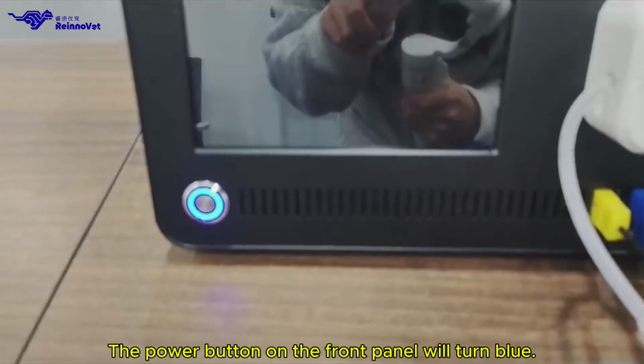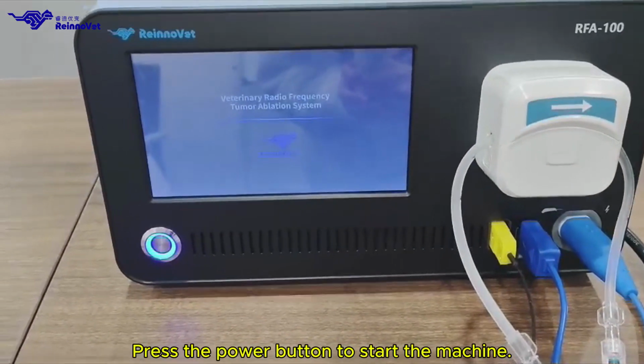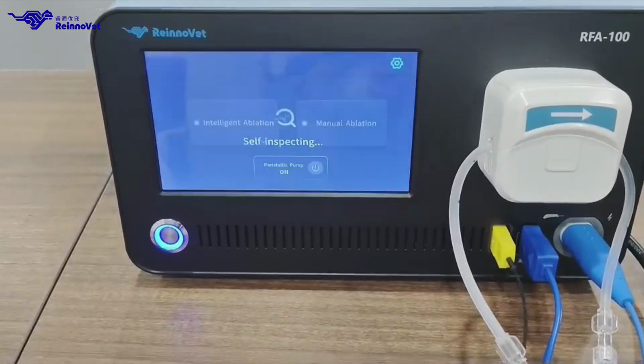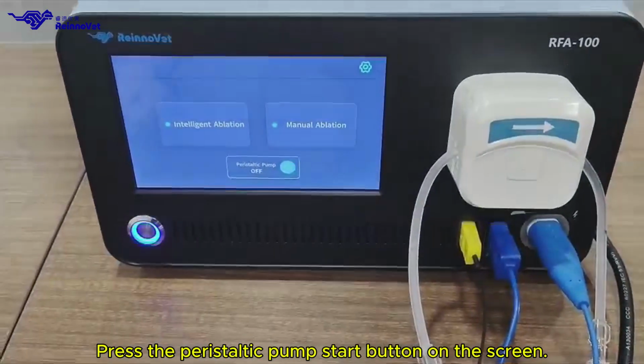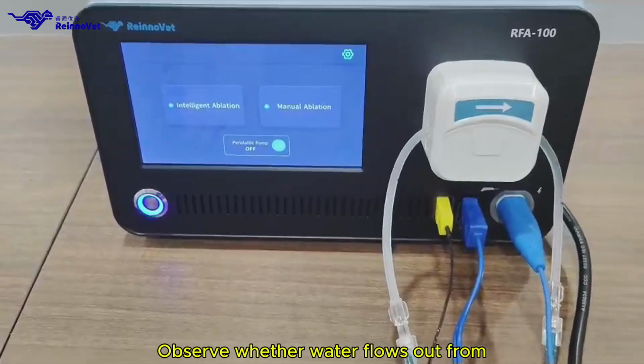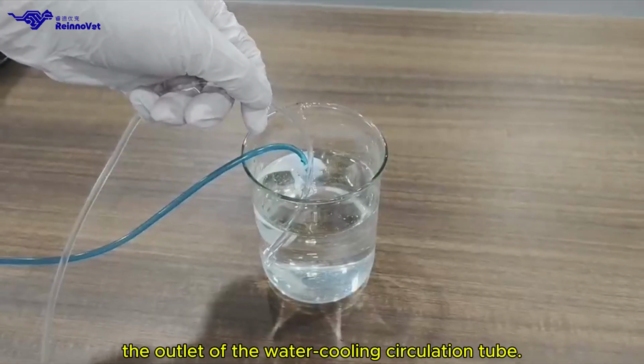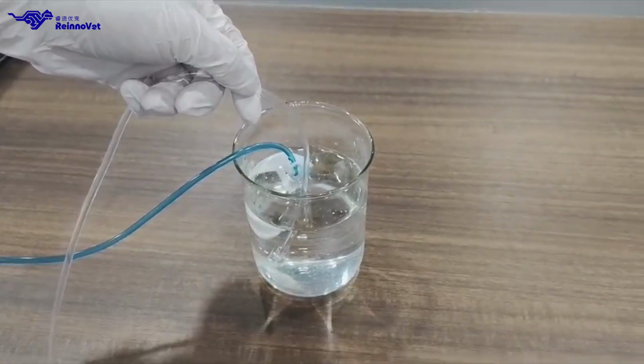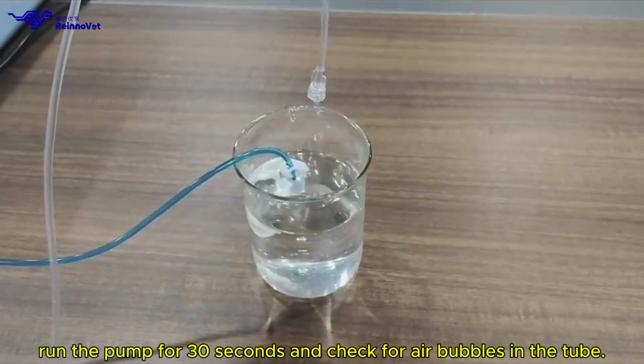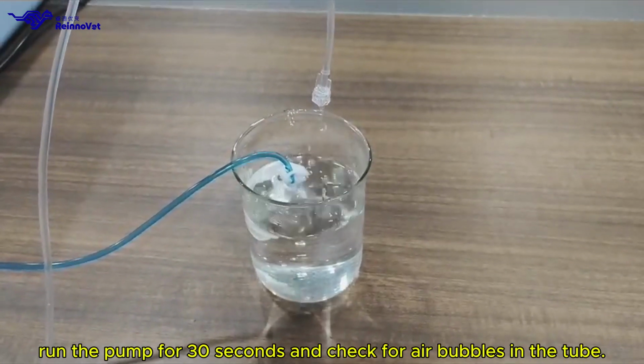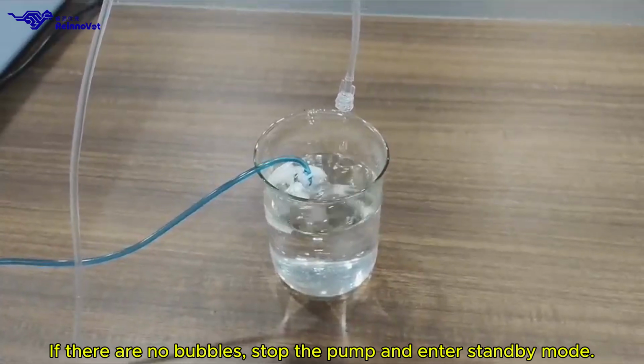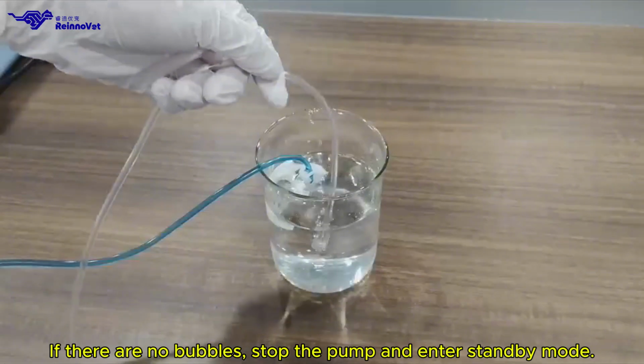Turn on the switch on the back of the generator. The power button on the front panel will turn blue. Press the power button to start the machine. Press the peristaltic pump start button on the screen. Observe whether water flows out from the outlet of the water cooling circulation tube. If water flows, run the pump for 30 seconds and check for air bubbles in the tube. If there are no bubbles, stop the pump and enter standby mode.